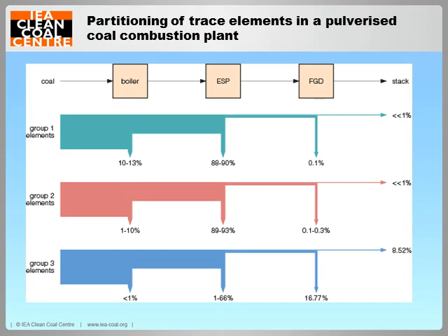The investigation demonstrated that not all trace elements enter the system with the coal. Some boron was introduced in the water used to slurry the FGD sorbent. The FGD limestone introduced not only considerable amounts of lead and other trace elements such as arsenic, cadmium, manganese, but also iron, magnesium, silicon, and titanium.